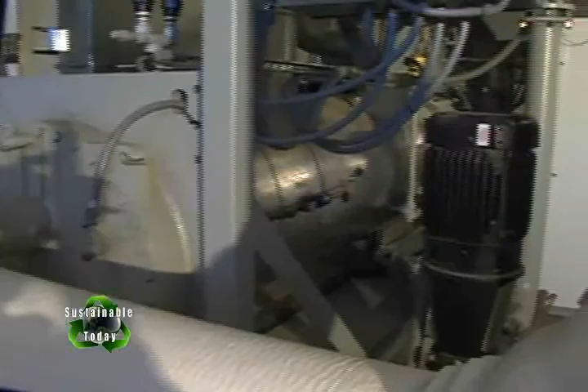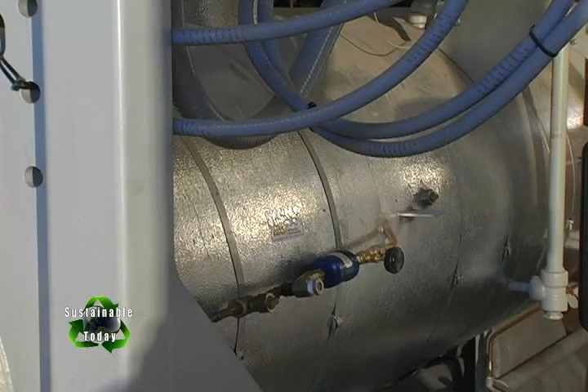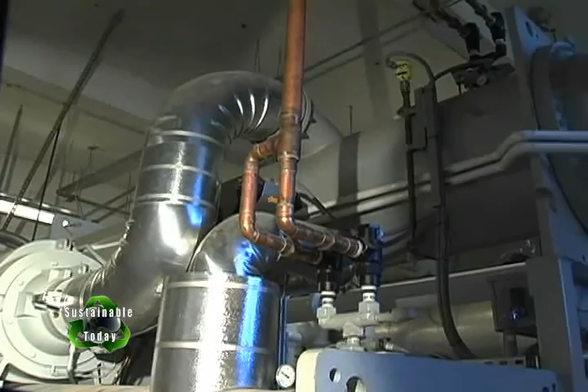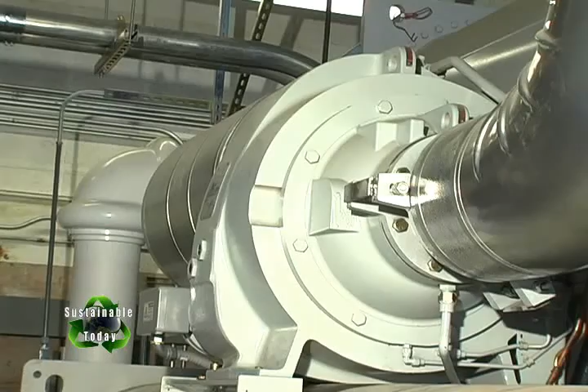Since water doesn't boil until 212 degrees, and we're below that with our operating temperatures, we use a secondary fluid. In this case, it's isobutane. This is called a binary plant. It uses a secondary fluid to turn the turbine rather than a primary system, which would use dry steam. If we were able to use dry steam, we would be far more efficient because all we would have would be the hot water, and we wouldn't have to go through the process of recondensing the fluid. So a binary plant runs off of a secondary fluid that boils at a lower temperature, and therefore we are able to turn the turbine with the steam. It's just not water steam.